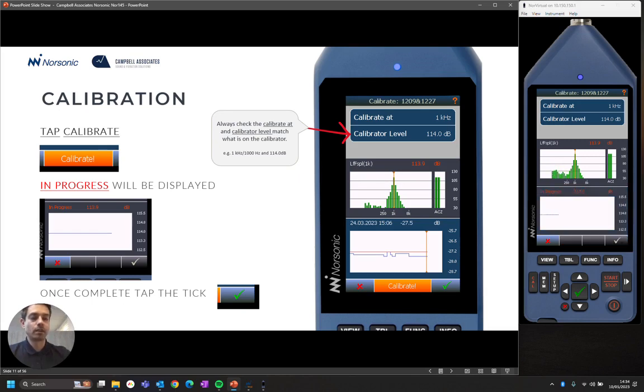You'll start to see the line move through. It's now saying in progress, and you should also be making sure that the calibrate at is at 1 kilohertz and the calibration level is at 114. Once it's completed, it will illuminate orange again. You just need to press the tick key to save this. And what's great about these meters is it does keep a level versus time history of all the calibrations to ensure that we have good repeatability in the meter.